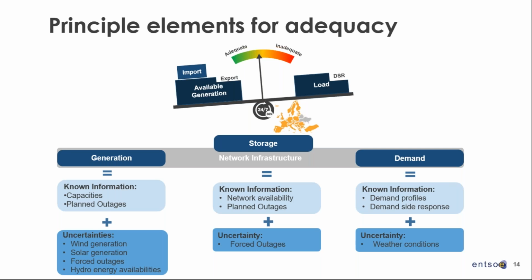And for the wind and solar generation, we have a set of reanalysis data with hourly values that are correlated between the wind, solar, and also hydro and temperature, correlated in time, from one hour to another, but also in space, from one country to another one, which is important. We consider also the forced outages of the generators.